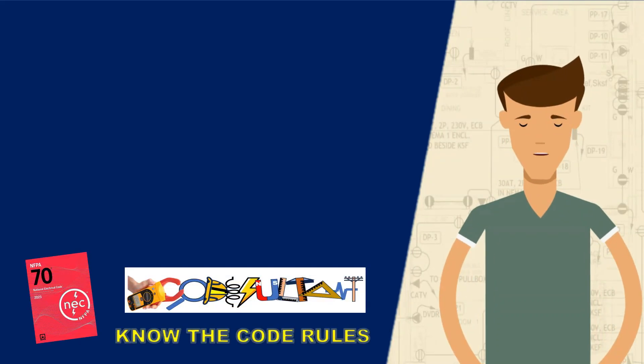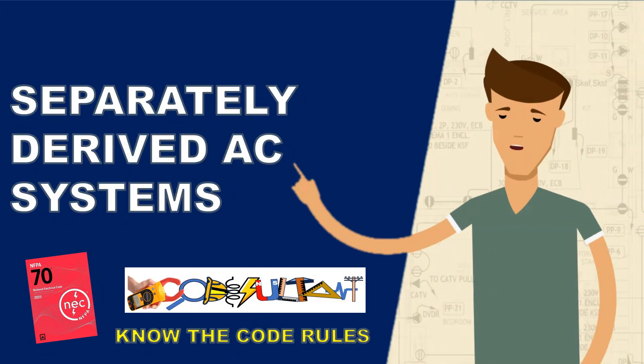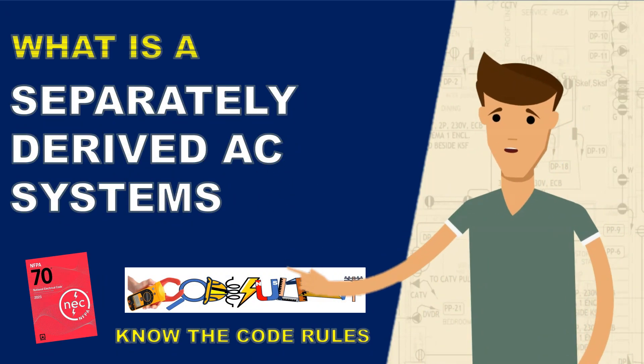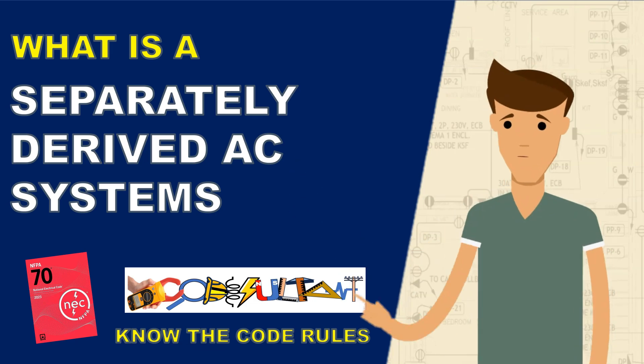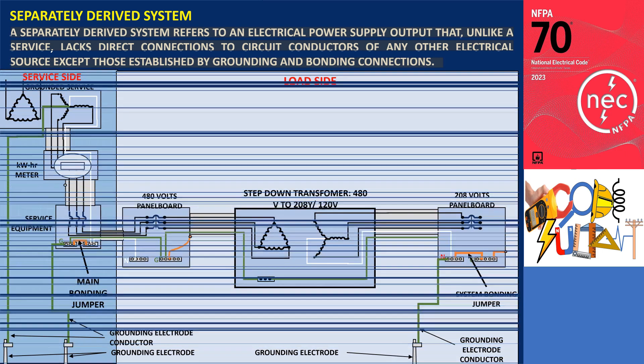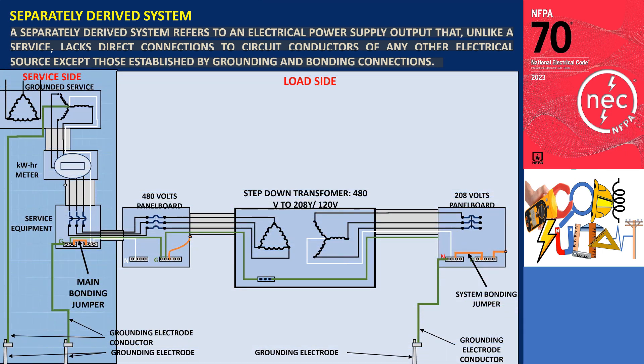Before proceeding to the following sections, let's ensure we understand what a separately derived system is. A separately derived system refers to an electrical power supply output that, unlike a service, lacks direct connections to circuit conductors of any other electrical source.